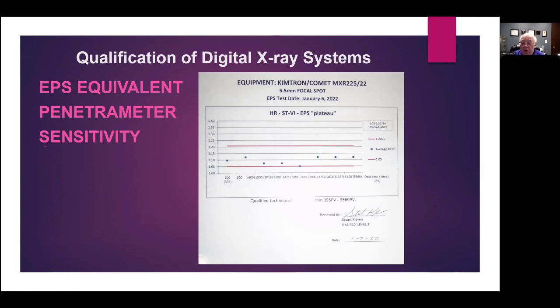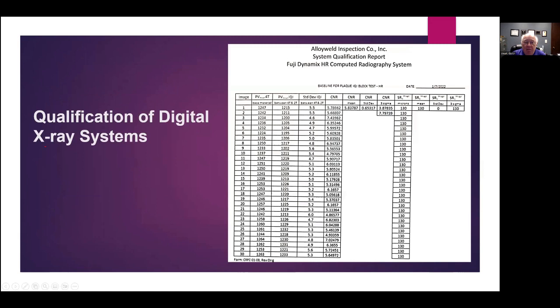So as you're doing images and you look at your image on the bottom, as we showed down in the corner on your image, if your pixel value falls outside your plateau, then it's not qualified. So we document our baseline, your 30 days, and then your standard deviation each day, your CNR, your basic spatial resolution.